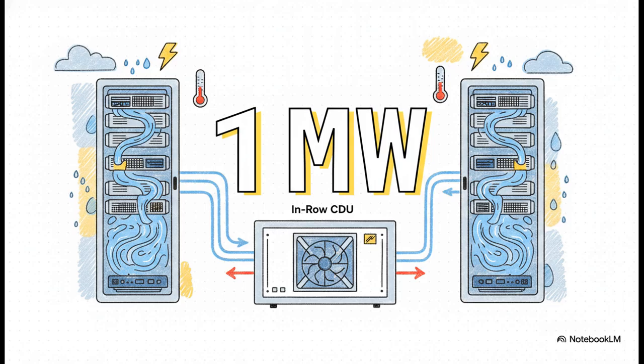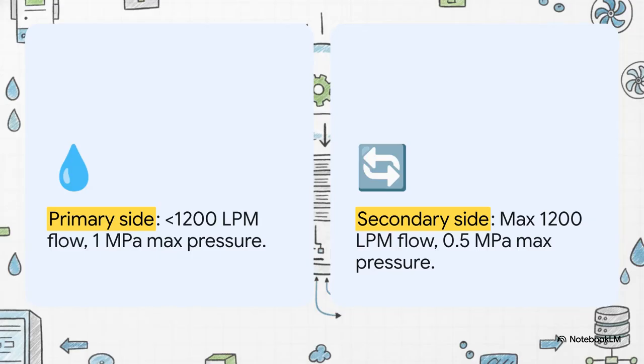It perfectly represents the incredible scale of the system you need to keep fully populated liquid-cooled racks operating at peak efficiency. Now, to understand how it actually moves all that heat, we have to look at the dual-loop plumbing. On the primary side, your facility water, we have a supply flow rate of just under 1,200 liters per minute, operating at a maximum pressure of 1 megapascal.